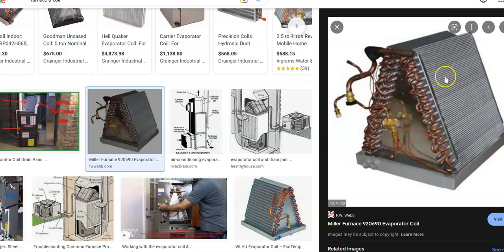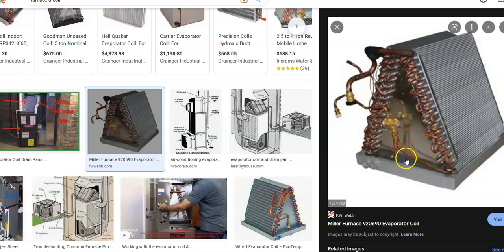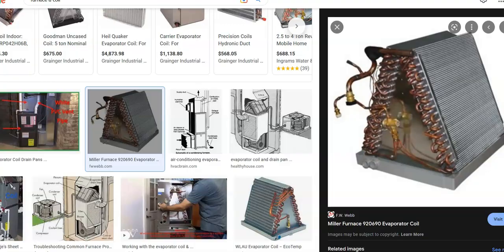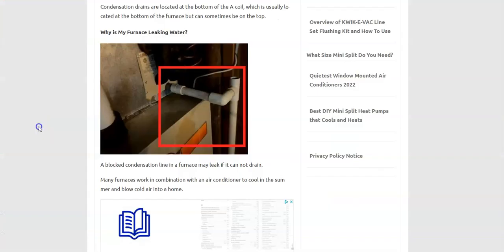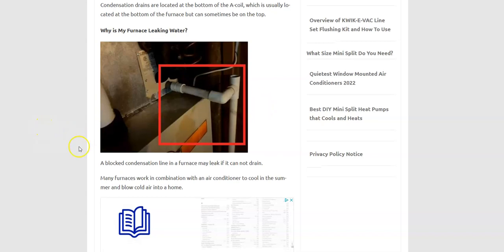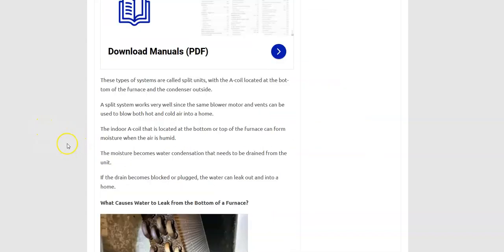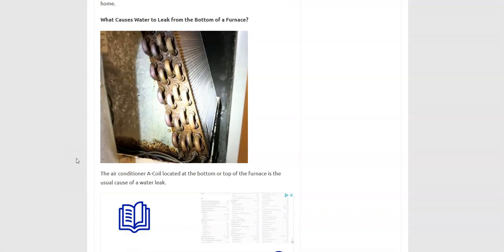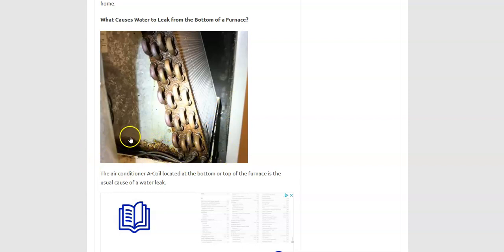If it is plugging up because of that, then you might have to clean out or run some water through this A-coil, which is a good idea to clean this A-coil anyway, running water. You don't want to bend the fins, but you flush it out and get all this gunk that might be inside the bottom of this pan. There might not be, it might just be clogged up because of algae or something like that. Algae likes to grow in these things and you can use Clorox to help keep the algae down. Basically the first thing you do is go locate the drain line and then try to figure out why or where it's plugged up at. You could take the bottom or the top off the furnace to look at the A-coil itself and look at this drain pan that's down here and see how plugged up it is.